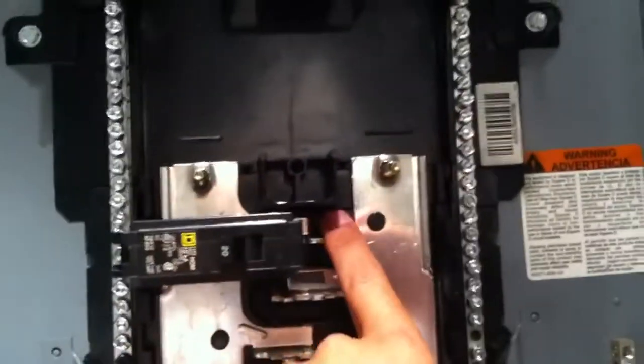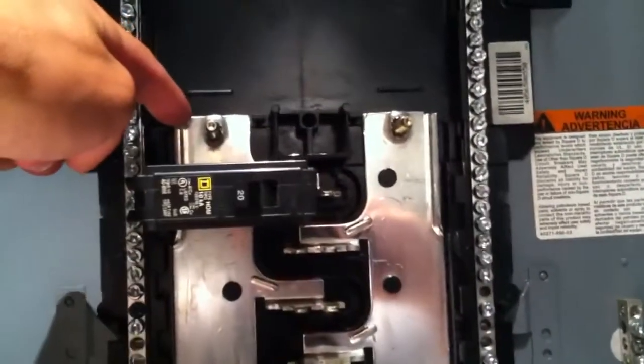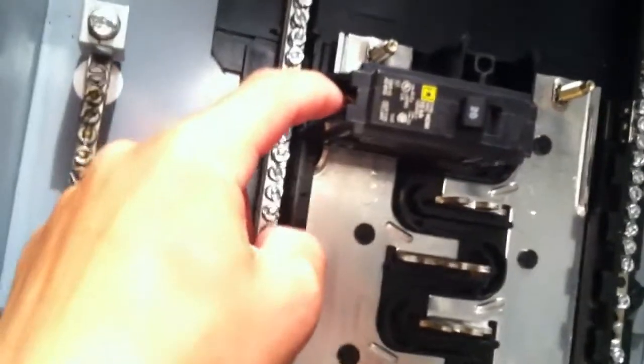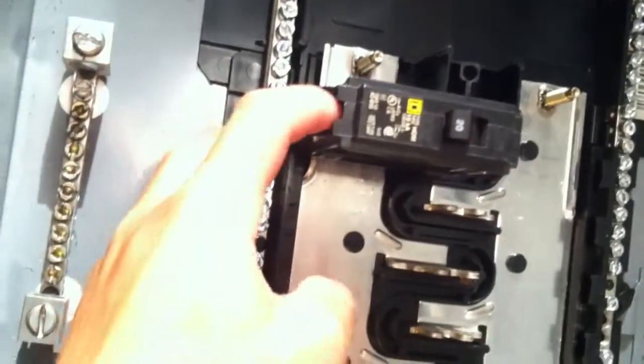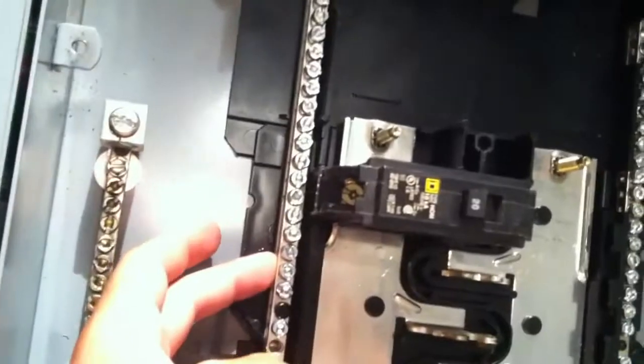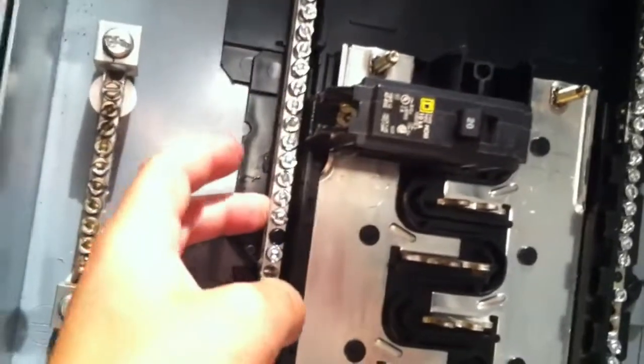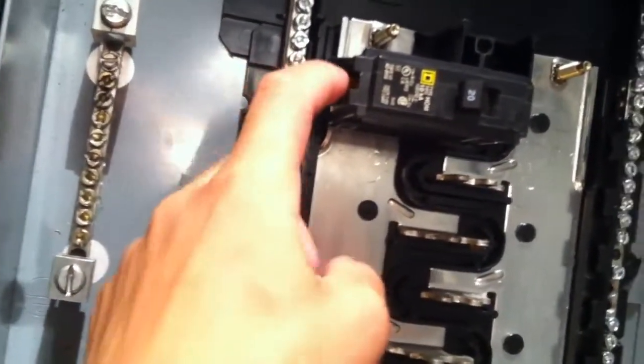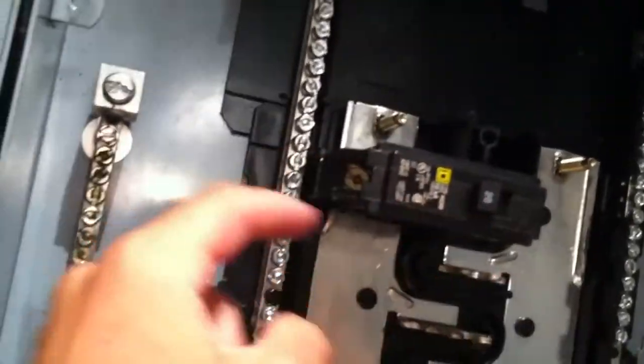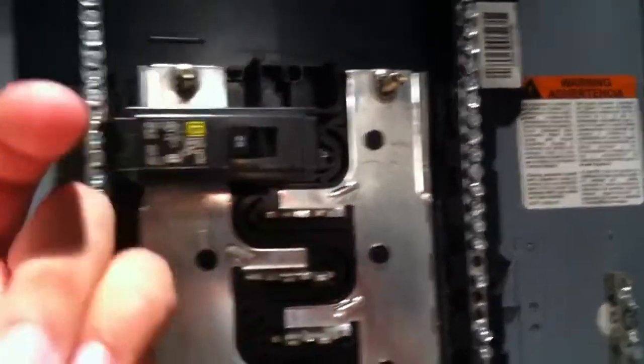This is a 20 amp breaker, so this is what you'd find in a typical 20 amp circuit. It's going to pull power from this phase, and output it through here, so this is 120 volts. The other leg is referenced to this neutral bar, so you'll have a neutral going to a light socket or light switch, whatever the case may be - microwave, dryer, oven, whatever it is. That's going to get its power from this screw right here, with a maximum capability of 20 amps, and if it pulls more, the breaker trips. So you'd be using the lug here from the breaker and then the neutral line - that's how that works.